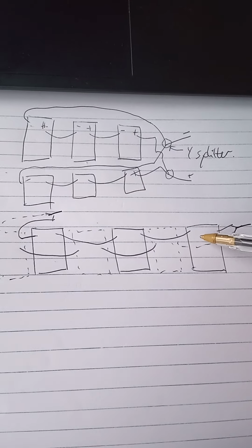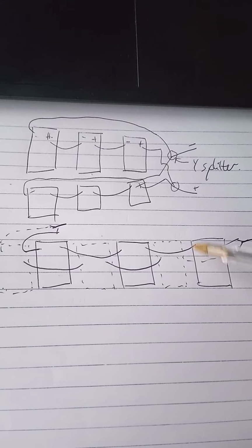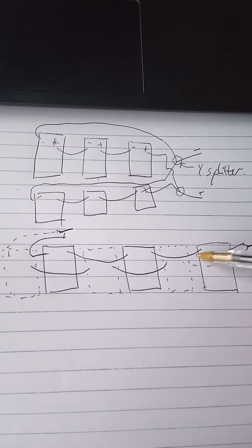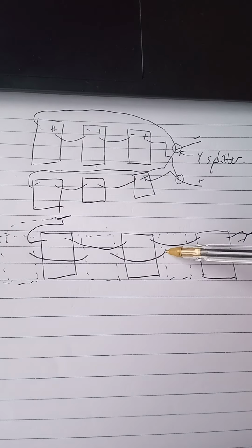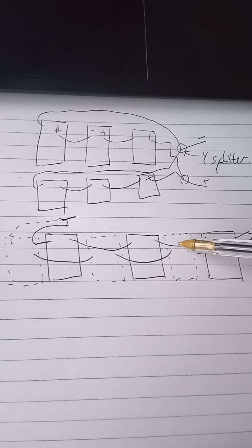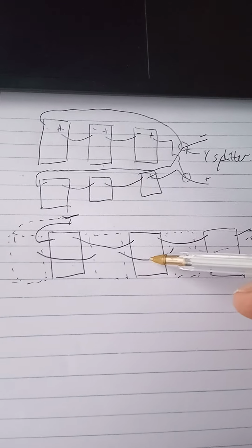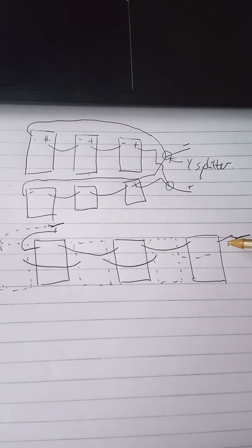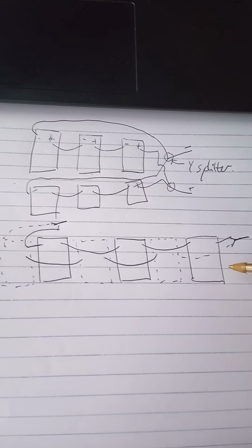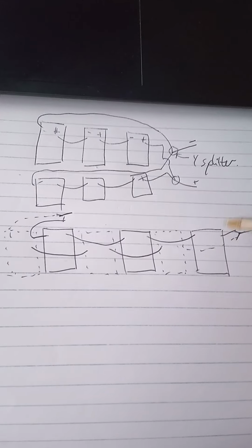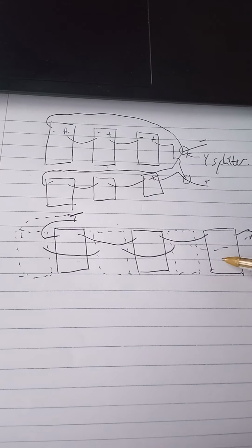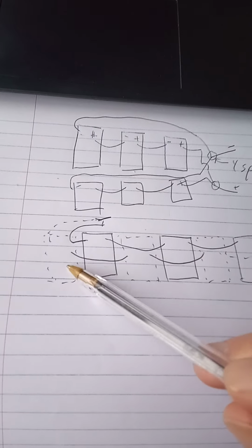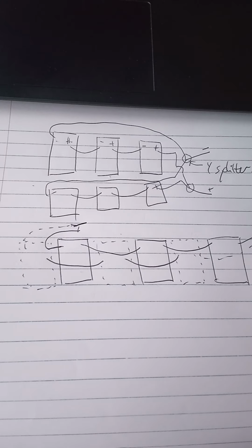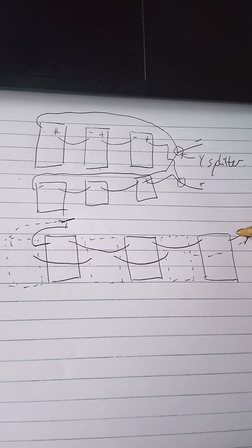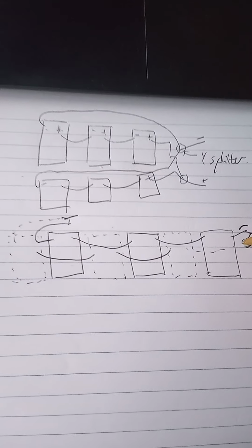And the wire on the back of Victron solar panels, for example, is just long enough that you can make this jump with a panel in between. This is using the 175 watt panels without putting too much strain on the cables. It is important though that you cable tie them in so that the connections aren't bearing the load of the cable, and also the vibration and wind movement of the cables, which can damage them. So if you're going to do series parallel and you've only got space for one row of panels, drop them in between and you'll be able to reach the wires without having to create an additional wire to extend this section here. That might be my top tip for you.